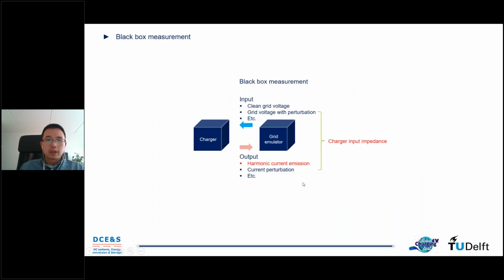One way to do that is the so-called black box measurement, which means if you have a charger, you can connect it to a grid emulator. Once the grid emulator generates clean grid voltage, you can extract the harmonic current source from the output or input current of the charger, depending on how you define the direction. You can also use the grid emulator to generate a voltage perturbation. As a response, the charger will output a current perturbation. Then the ratio between the voltage perturbation and current perturbation will be the input impedance of the charger.